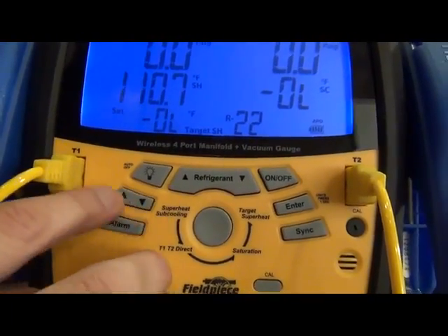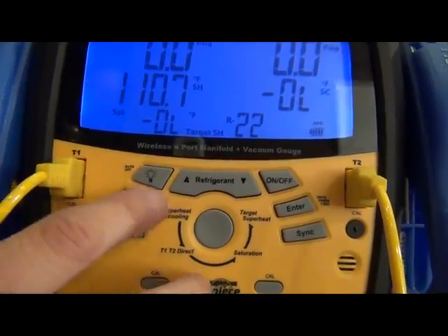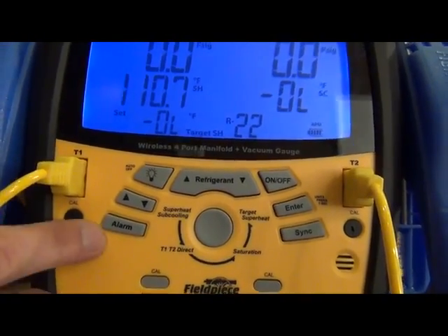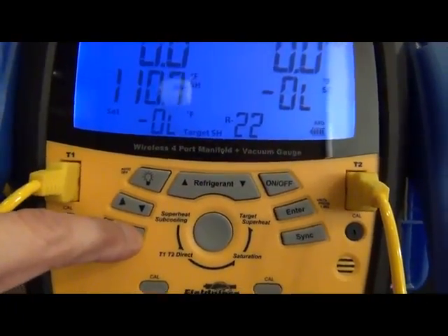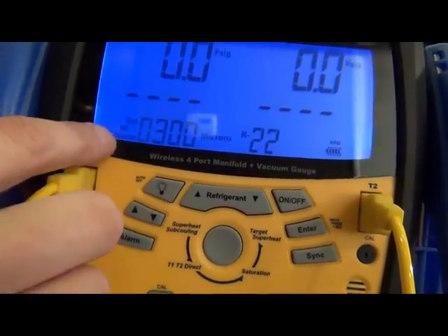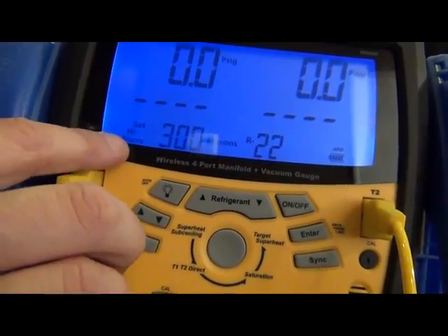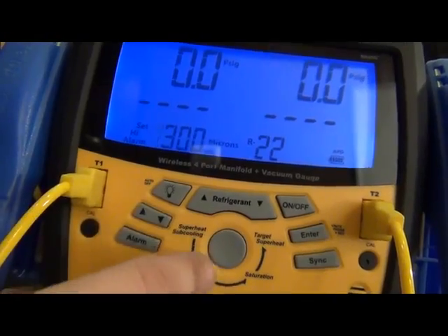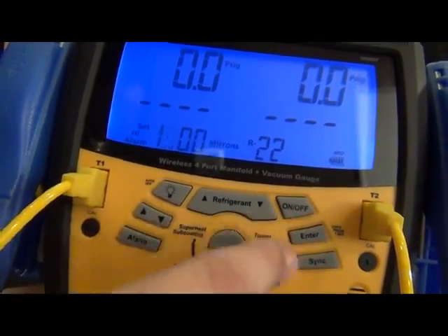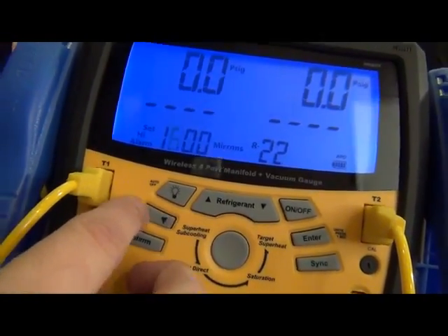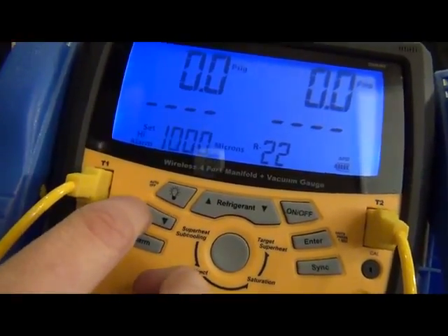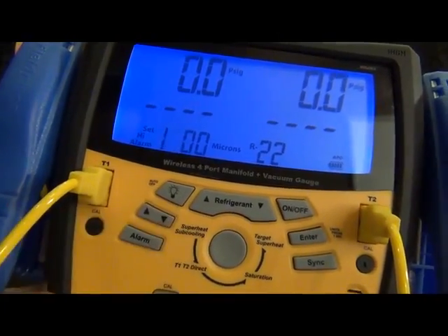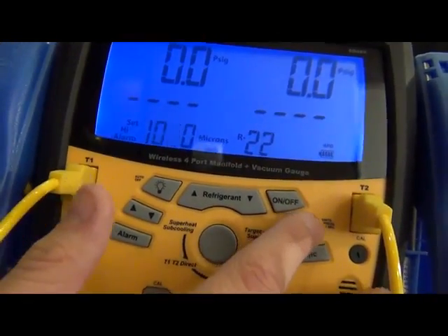The arrow button, that's used for a couple of different things when you're programming your micron alarm with this button. So if I hold down the alarm button, it gets into the high alarm mode. So what this is going to do is I can set this to, let's say, a thousand microns.